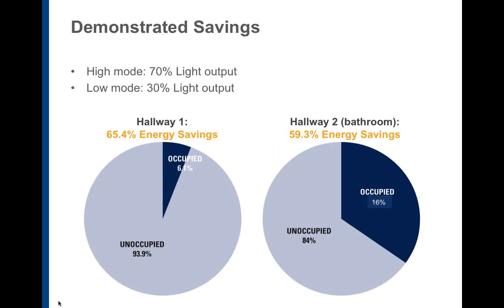Collecting feedback from this system and measuring, and we can monitor on a daily basis, we found that, of course, the bathroom hallway is a little bit more occupied at 16%, but what we formerly considered a high traffic area was actually occupied only approximately 6% of the day, achieving a 65.4% energy savings. Of course, you'll notice at the top it says high mode is 70%, low mode is 30%. So we did extend beyond that 150 best practice to consider 70-30 as providing ample illumination for the space and 30% when no one's around.